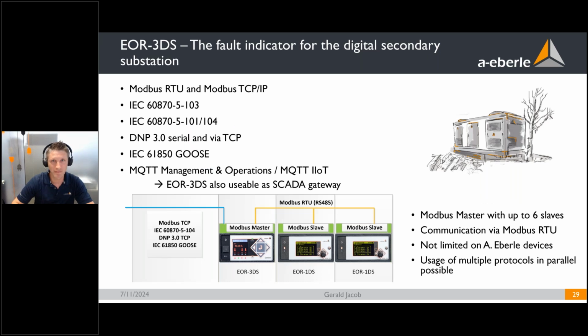Some words about protocols. I also already mentioned all the protocols the device offers. So not only serial protocols, but also Ethernet-based protocols. And I just want to emphasize here that regarding the serial protocol Modbus RTU, the device can also act as a Modbus master. Not only for EOR-1DS devices, but of course this is the solution we always mention. So if you have an application where you want to use, for example, 104 protocol without an RTU, you could install one EOR-3DS as a Modbus master that offers 104 protocol and in addition reads out all the data from the Modbus slaves and acts as a SCADA gateway in the direction to 104 protocol.